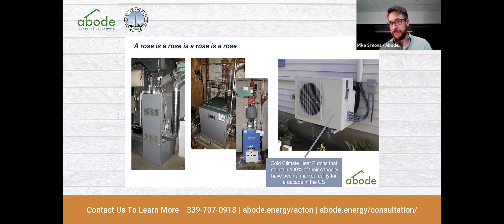Forced hot water boiler could be 65,000 BTUs or could be 40,000 BTUs. If it's a 40,000 BTU boiler, it's not going to heat your home on the coldest day of the year. If it's a 70,000 BTU boiler, sure. With heat pumps, it's no different. When you go and look at the manufacturer's specs in the submittals, they have heat pumps that could be 12,000 BTUs, 24,000 BTUs, or 60,000 BTUs. So all a heat pump is, it's just going to be generating heat. It's not a matter of technology, it's a matter of sizing that's going to be really important.